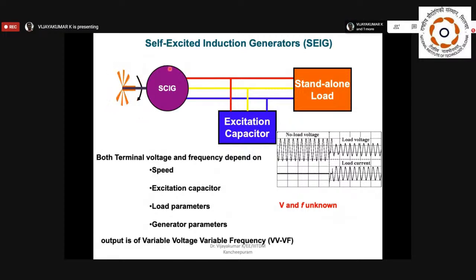Even if you operate above synchronous speed, you will not get any voltage at the stator terminals. Why? Because you are not having any magnetism, since the loads are RL. These RL loads will not provide any magnetizing current to the machine, so it will not generate power. For that purpose, you need to connect capacitor banks. These capacitor banks will provide the magnetizing current to the machine, so it will build up the voltage at the stator terminals to supply the loads. In the machine we have the residual voltage. With the help of the residual voltage and the capacitor, the voltage builds up at the stator terminals, and you can connect your load.